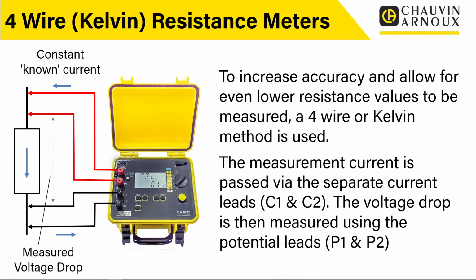And then because of the voltage terminals, we can use a high impedance voltage meter effectively to measure the volts drop. So we can use a very accurate high impedance voltage meter, and that will again not be affected by things like contact resistance, because it's a very high impedance measurement circuit. We can accurately measure the voltage, and again, same thing, a bit of Ohm's law, and we get the resistance. But by separating the current path, where we can pass this current through, and the potential measurement, the sensing part of the circuit, we can increase the level of accuracy that we're going to get. This is the standard 4-wire or Kelvin type setup that we use, and this is standard on all really accurate low resistance meters.